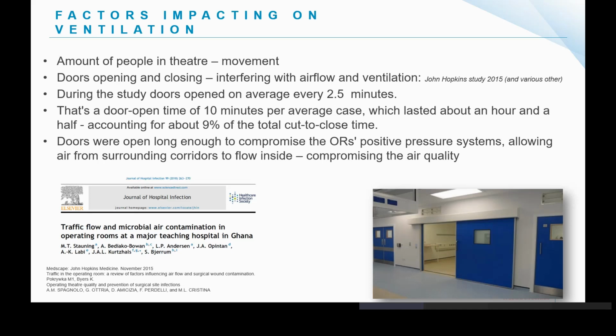So that amount of people in and out of theatre, the doors opening and closing, interferes with the airflow and ventilation. And they did a similar study at Johns Hopkins where they looked at how many times the theatre doors open. During that study, they found that it opened on average every 2.5 minutes. And every time you open the doors, it compromises the positive pressure system, allowing air from surrounding corridors to flow inside the theatre, which is not clean or filtered air and can potentially contaminate the area.